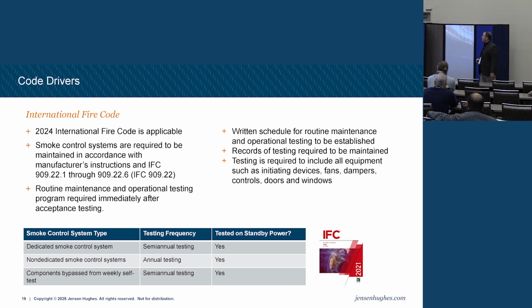Smoke control systems are required to be tested in accordance with the manufacturer's literature and that initial design document, right? So I just said the manufacturer. Well, maybe now I need the manufacturer of the air handling equipment, possibly, or I need the manufacturer of the fire alarm system. If it says manufacturer of fire alarm, is it okay if I have a licensed vendor who is licensed to work on that system in lieu of the manufacturer? Sure, right? That's the same intent.